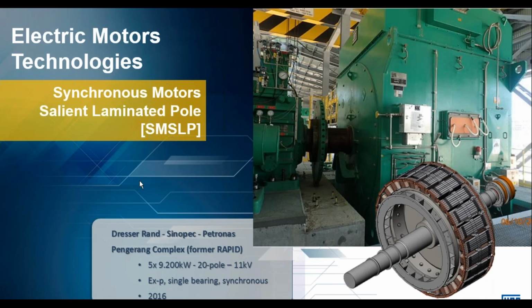The next type of synchronous motor that we're going to discuss is a salient laminated pole design. You can already see just by looking at it, we do not have a uniformly distributed rotor winding design, and so your air gap torque is not uniform. And here you need to do an additional analysis because of the oscillatory torque created by a non-symmetric magnetic circuit. It's just an additional due diligence that needs to be done on these machines to ensure that we do not have a torsional vibration issue inherent to the design.